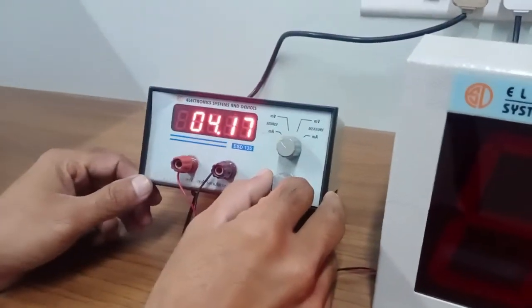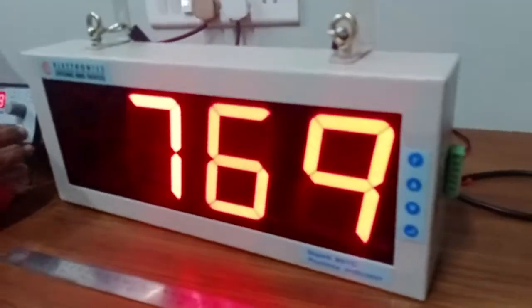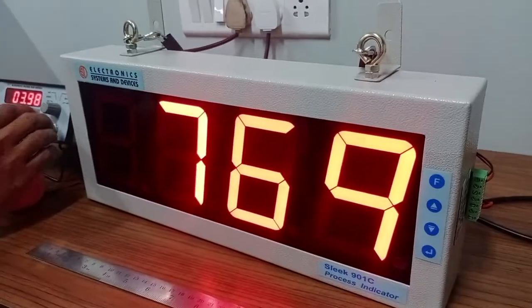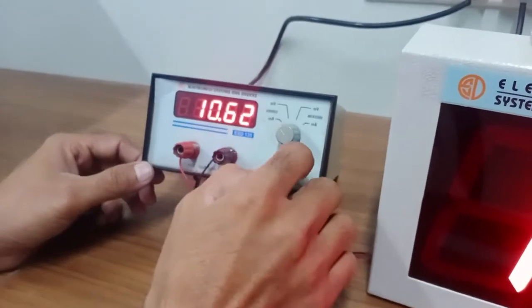Then it asks for the zero. Here you have to feed 4 milliampere. You'll get some reading, you have to press enter. Then it goes to the span reading. For span reading, you have to feed 20 milliampere.